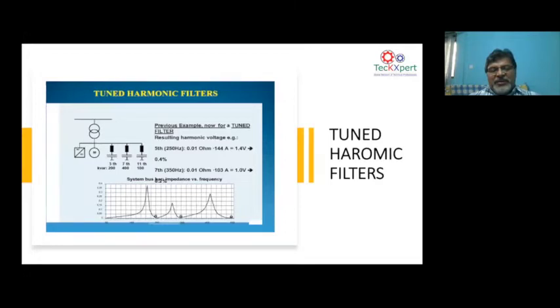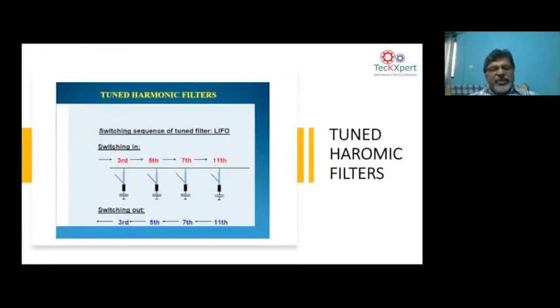As I said in the previous slide, either you put a passive broadband filter at the output of the drive and remove the entire harmonics coming out of the drive, or you put a passive filter at the main LV switchboard and filter the total harmonics in the network. But the passive filter solution has its own pluses and minuses. So I won't say putting a passive filter is the best solution. Whenever you go for a passive filter, you always have to properly design and decide what the right solution is and where you should install it. Go to the next one. Yes, this is a passive filter being shown. Go to the next.